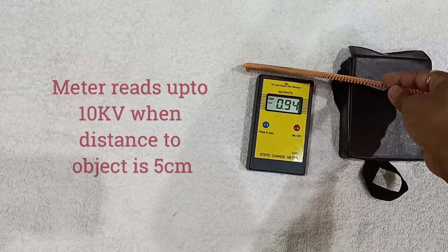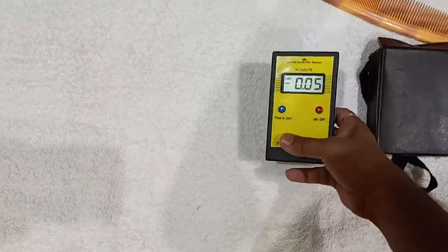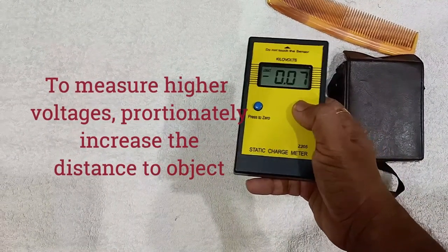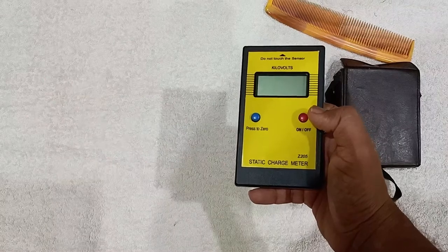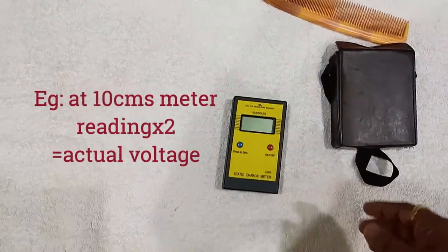The meter reads up to 10 kV when the distance to object is 5 centimeters. To measure high voltages, proportionately increase the distance to object. Example: at 10 centimeters, multiply the reading by 2 to get the actual voltage.